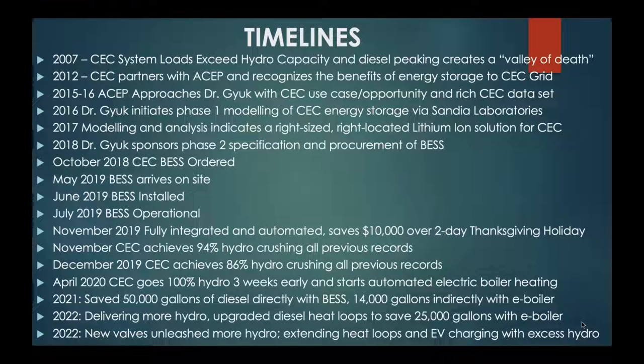It arrived in May of 2019. We had it fully commissioned on the ground in July, then operated it manually for several months to work all the bugs out. On Thanksgiving week 2019, we put it into full automated operation. In 2021 it saved us 50,000 gallons of diesel fuel directly, and freed up enough hydro to save another 14,000 gallons with our electric boiler, and we've since made further gains.